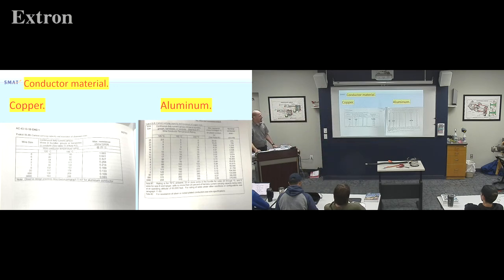So that's part of how copper is a better conductor. So you'd say, well, why would I ever do aluminum then? Well, the answer is if I had, I don't even know what gauge this is, 0, something like that. If I had the same length of copper wire, it's going to be much, much heavier than my aluminum wire. So if I had to run something like this all the way to the back of my 747 airplane, or where you'll sometimes see it on small aviation is if the battery's in the tail of an airplane, they'll do that for weight and balance sometimes, and you got to do a 30-foot run to get the battery power all the way up to the engine and the starter.